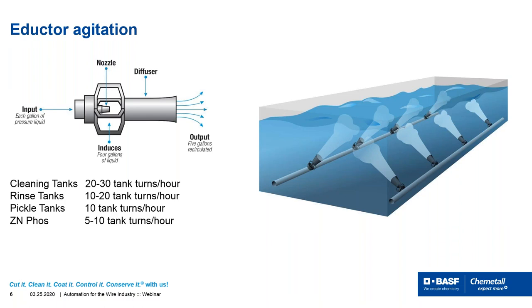Looking at the different setups, for a cleaning tank the pump may be required for 250, 260 gallons a minute. Your rinse tanks would be less. You could go with a smaller tank and fewer eductor nozzles, because typically 10 to 20 tank turns is enough. Then for your zinc phosphate tank, that may only require a pump doing approximately 75 to 100 gallons a minute in order to keep everything completely agitated. This is a very convenient setup to do. The most important thing is to make sure your eductors are strategically placed so you hit all the spots and get good agitation, with no dead spots in the tank.